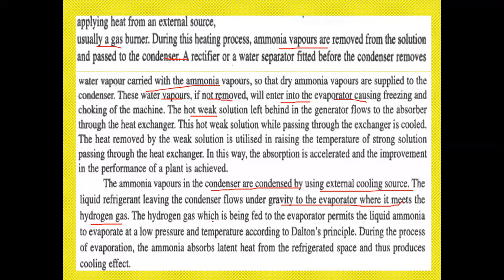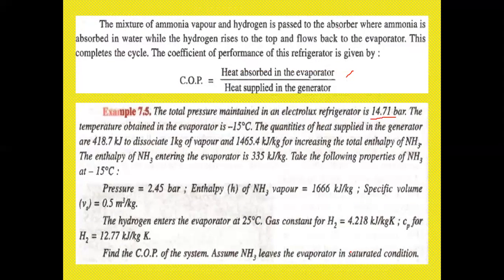Next, the hydrogen gas which is being fed to the evaporator permits the liquid ammonia to evaporate at a low pressure and temperature according to Dalton's principle. So during this process of evaporation, the ammonia absorbs the heat from the refrigerated space and thus produces the cooling effect. That is the operation of this system. Now, the mixture of ammonia vapor and hydrogen is passed to the absorber where ammonia is absorbed in water while hydrogen rises up to the water top and flows out to the evaporator.